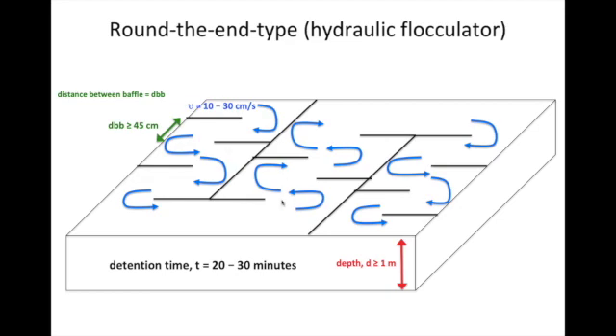I also like to say that the distance between the end of a baffle to the wall should be 1.5 times the distance between baffles.